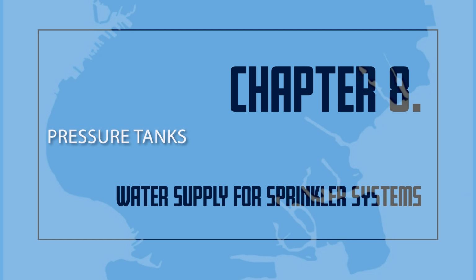Pressure tanks are often used in situations where an adequate amount of water can be supplied by a public or private source, but the water pressure is not adequate. The pressure tank gives a strong starting pressure for the first sprinklers that open. The flow from the tank may be used while the automatic fire pumps begin to increase the water supply pressure. Pressure tanks are often used in tall buildings that need extra water pressure to supply the highest line of sprinkler heads. The pressure tank supplies these sprinkler heads until the fire department begins pumping water into the sprinkler system.